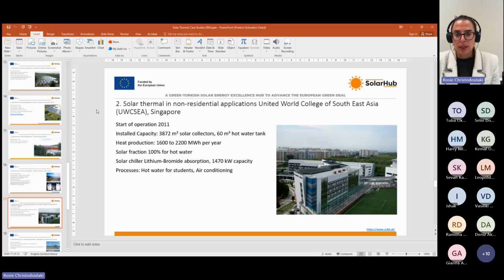It can produce heat, and the annual production is 1,600 to 2,200 megawatt hours per year. This solar thermal system can produce the whole hot water demand for this college for 1 year. So the solar fraction is 100%.